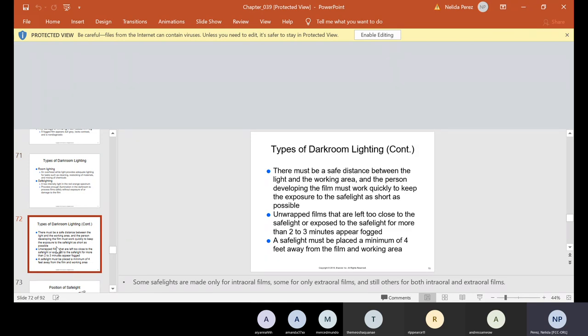Types of dark room lighting: room lighting is an overhead white light that provides adequate lighting for tasks such as cleaning, restocking materials, and mixing chemicals. Safe lighting is a low-intensity light in the red-orange spectrum that provides enough illumination to process film safely without damage. There must be a safe distance between the light and the working area, and the person developing the film must work quickly to keep exposure to the safe light as short as possible — also because in an office, if several people are taking films, the doctor may be waiting, so you need to move quickly.